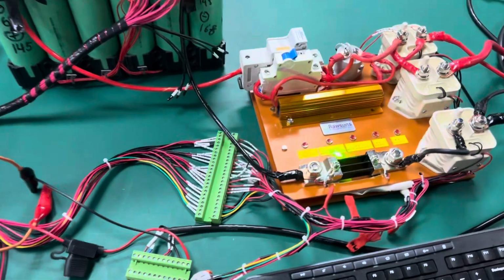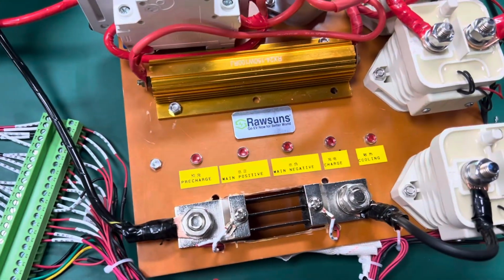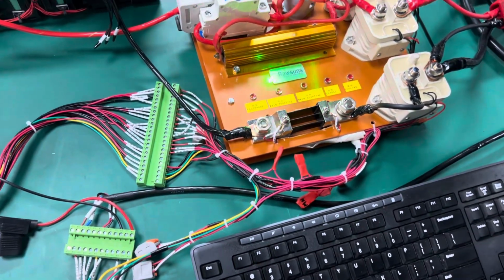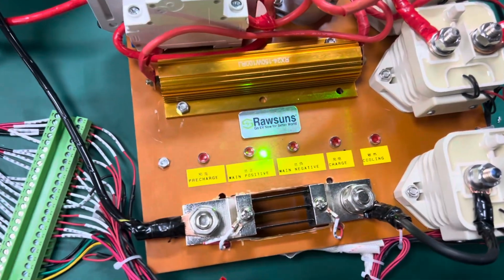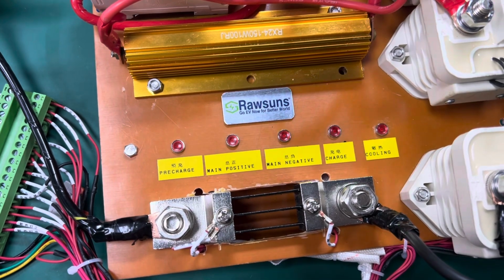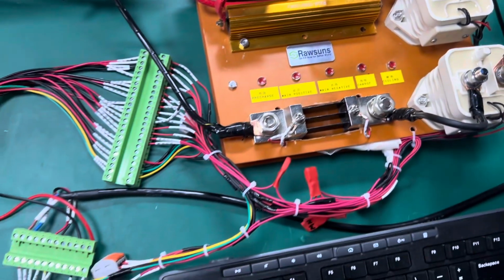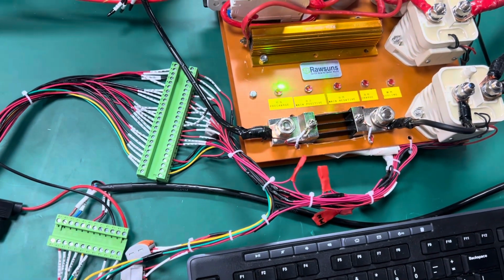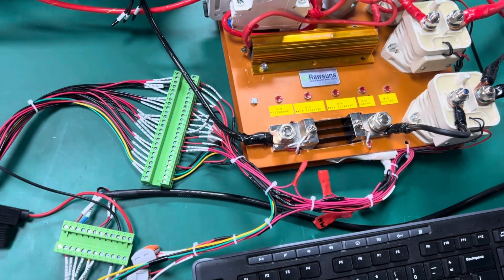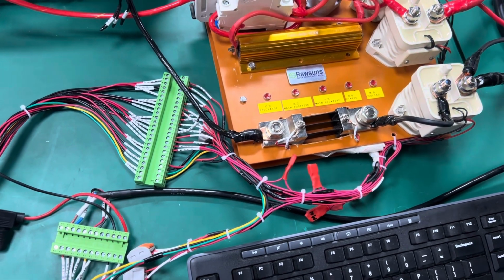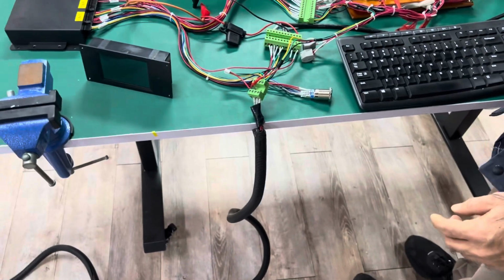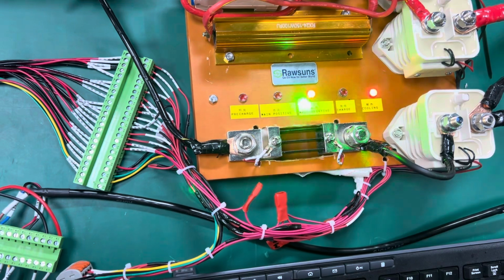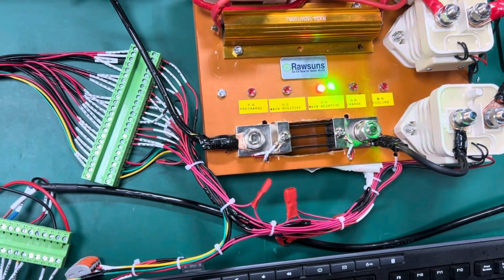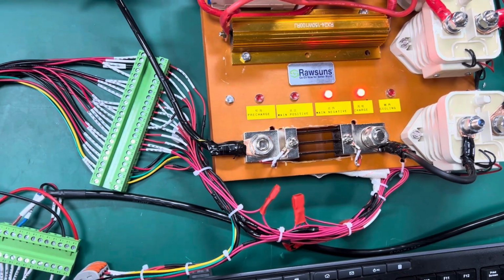And we have put some indicator lights on our test bench, and this one is for the pre-charge, and this one is for the main positive and main negative, and charge and cooling. Each light means that if the light is on, the relay is closed, is connected. Okay, you can keep the camera here. Now I press the button.